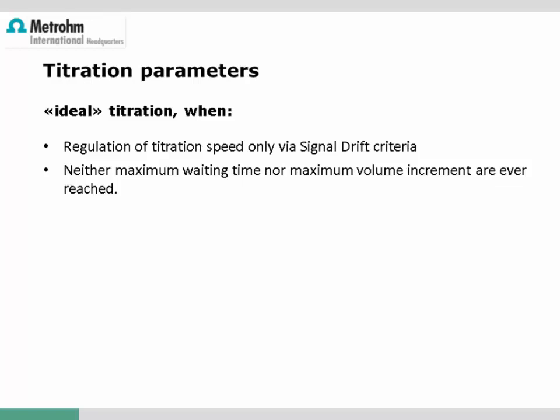How do you know you have chosen the best parameters for your application? You can check by looking into the measuring point list and comparing a few key parameters defined in the titration method. The titration should only be controlled through the signal drift criteria. Whenever the maximum limit value for waiting time or volume increment is reached, the signal drift criteria has been overruled and the electrode response may not correspond to the chemical reaction in the titration vessel. If the limit values are never reached, the titration parameters are well chosen — we call this a fully drift-controlled titration.